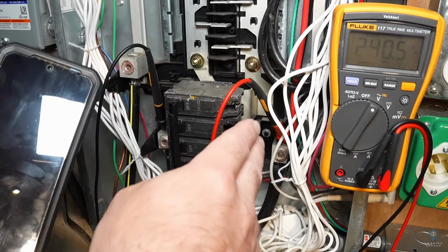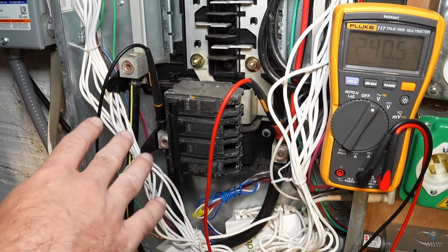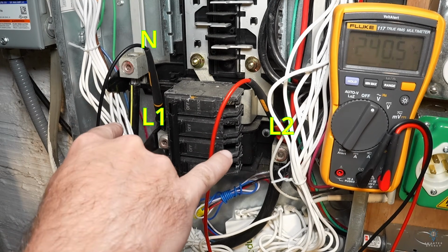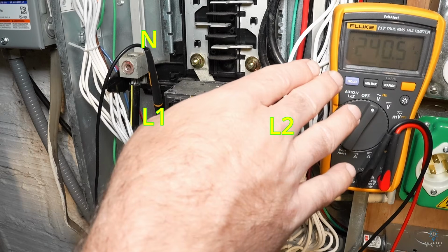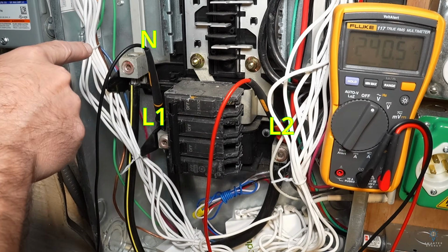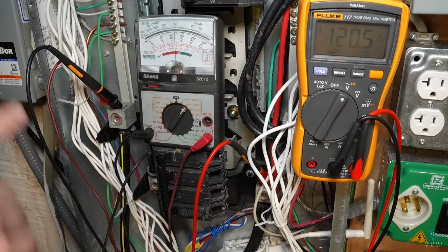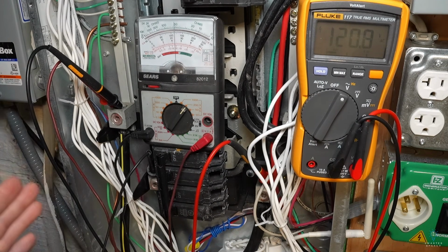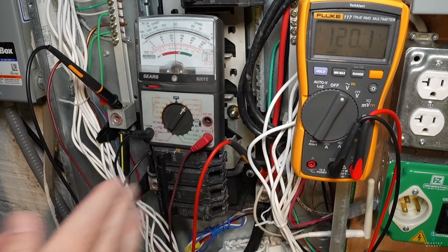All right, let's get back to it. So this test that we just did proved that our incoming lines are not deviating at all. We've got a solid 240 volts here. It's the reference to neutral that keeps swinging from side to side. So I've got this analog meter rigged up on line 1, and I've got this digital multimeter rigged up on line 2. Let me explain a little better real quick.